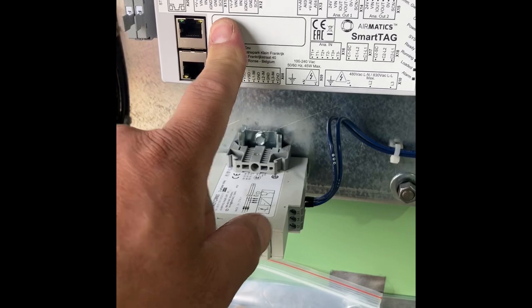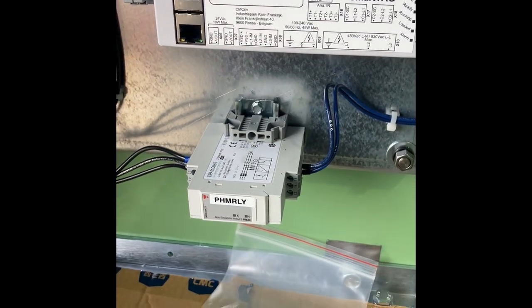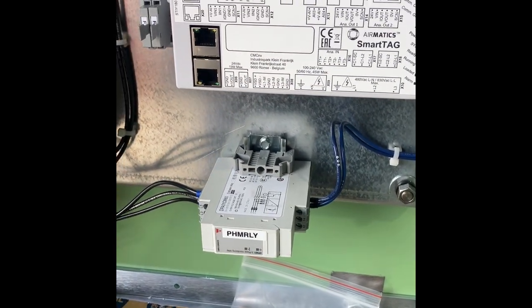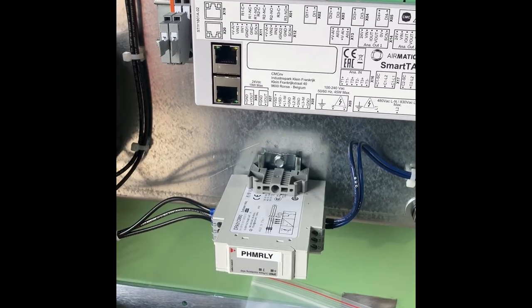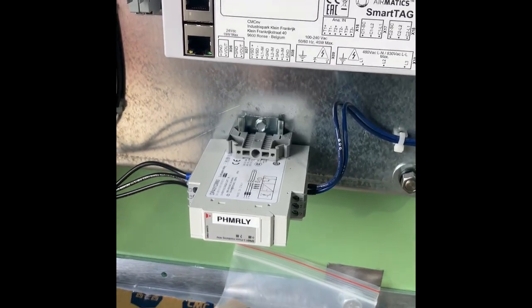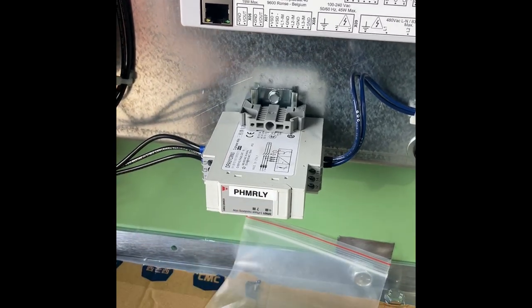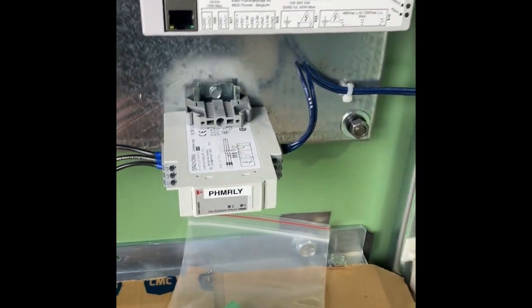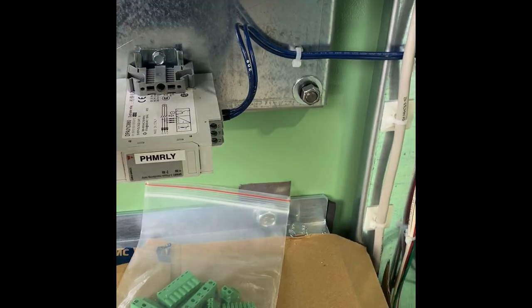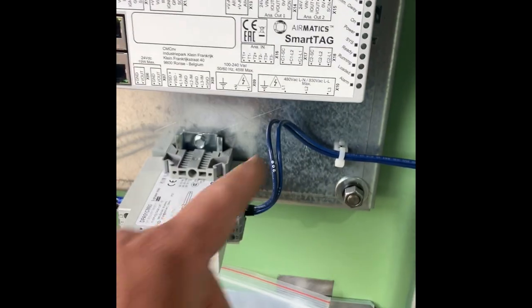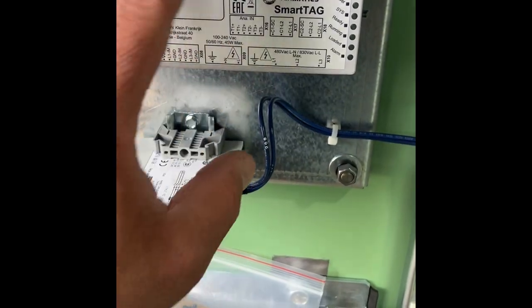Since we're using Modbus on this one, I won't need the air and discharge temperature sensor, so it'll just be the motor bearing and the ambient. We'll get the CTs wired in, the 120 wired in, the 480 wired in, and get all that connected. At that point I'll stop.